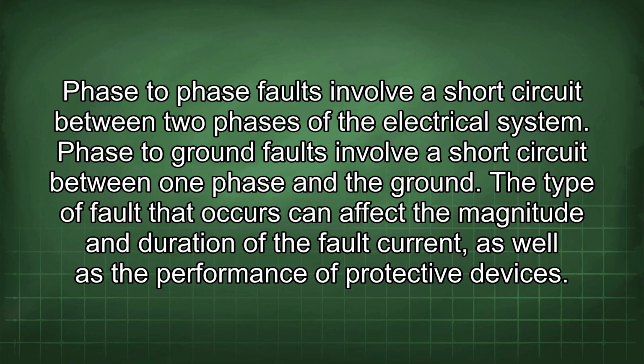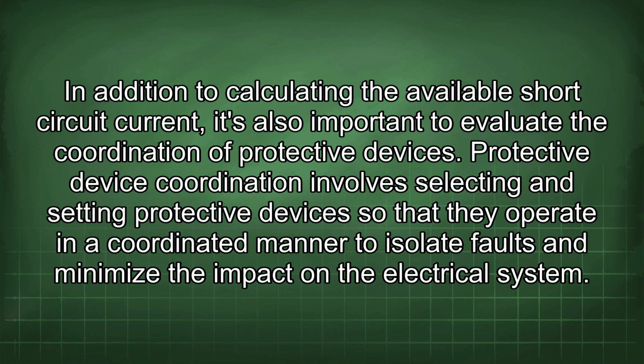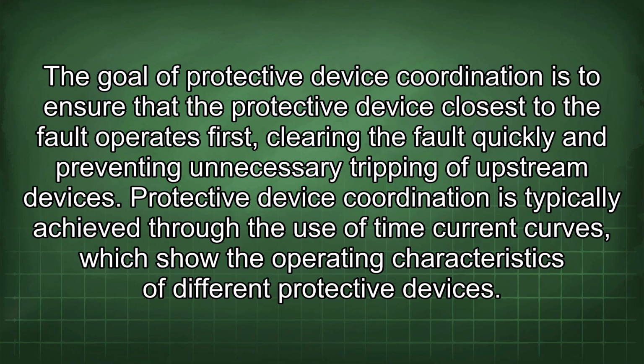performance of protective devices. In addition to calculating the available short-circuit current, it's also important to evaluate the coordination of protective devices. Protective device coordination involves selecting and setting protective devices so that they operate in a coordinated manner to isolate faults and minimize the impact on the electrical system. The goal of protective device coordination is to ensure that the protective device closest to the fault operates first, clearing the fault quickly and preventing unnecessary tripping of upstream devices.